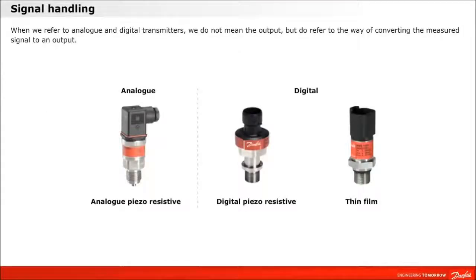Before we go through the technologies on the following pages, we need to clarify the difference between Danfoss analog and digital pressure transmitters. When we at Danfoss talk about a digital pressure transmitter, we do not mean the output. We refer to the way of converting the measured signal to an analog output. Currently, we do always have an analog output — only the converting is either in an analog or in a digital way.